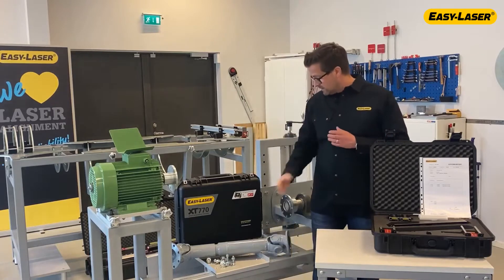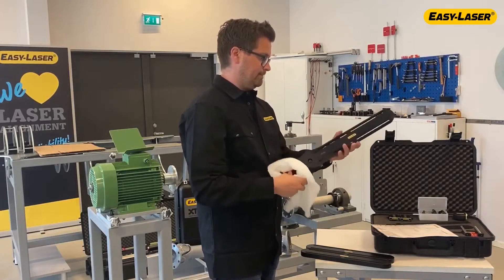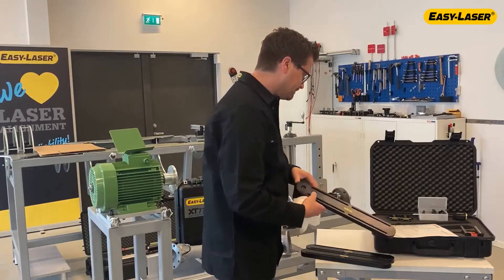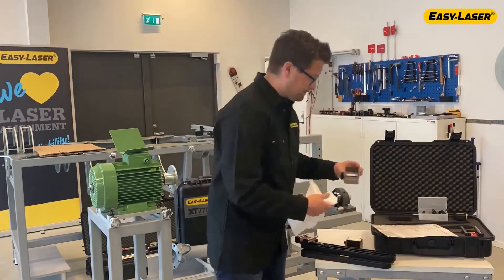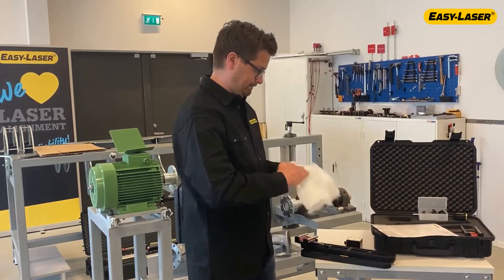As you can see, the coupling and shaft are removed, so let's get to work. Always start with cleaning and inspecting the set for any damage. The set contains a bracket for the movable machine and a bracket for the stationary machine. The bracket for the stationary machine consists of three precision grinded arms, two precision grinded magnetic bases and bolts for mounting these together. Make sure that the serial numbers on the magnetic bases and the arms match the numbers at the system report. They are approved and delivered as a set.